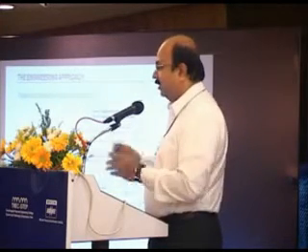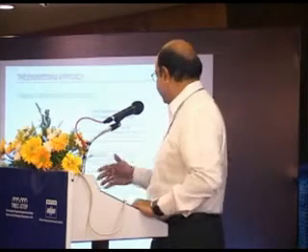Now, this picture is to actually, very important thing is to first assess what happened, what impact. This is not something like you do an R&M plain vanilla for each boiler that you are going to. So you have to first, for each boiler it may be different. Some boilers would have necessarily operated in a very nice operating regime, not going through situations where they have operated well over the temperature limits. So when you do that, you will actually can come up with creep damage and fatigue damage. Based on the data, you can see where the unit was operating, whether it was in the safe zone or the lines that you see.